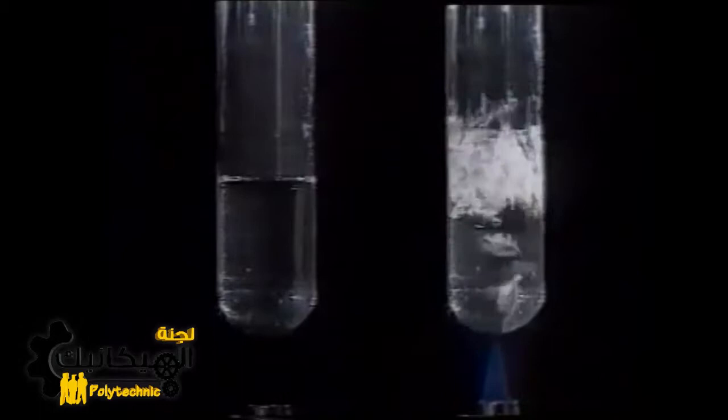To be able to control the water level in a boiler, you must first be able to measure it. But what exactly is meant by water level in conditions like this? Even at low, steady steam generation rates, when conditions are most stable, there's still considerable water movement and significant turbulence. When we talk about the level of still water, it is very clear what we are referring to. However, when the water is brought to the boil, bubbles of steam begin to occupy some of the water space, causing the overall level to rise, even though the amount of water hasn't changed. The more vigorous the boiling, the higher the level becomes.